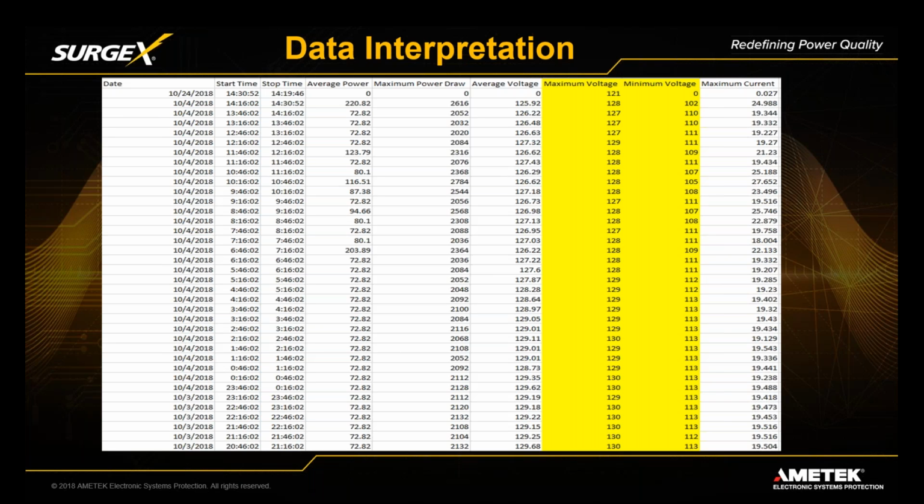So we see enVision was on one of those circuits, and it was swinging all over the place, high and low, which tells me that you probably have a loose screw somewhere in the breaker panel on a neutral bus or something like that. And this data really points to that.